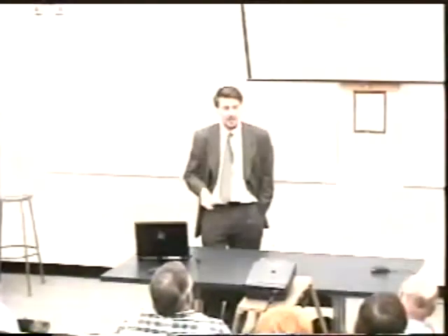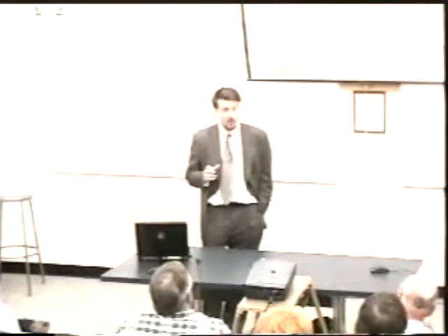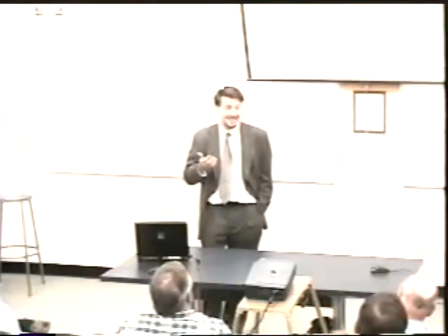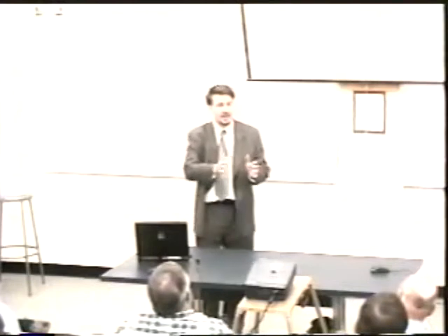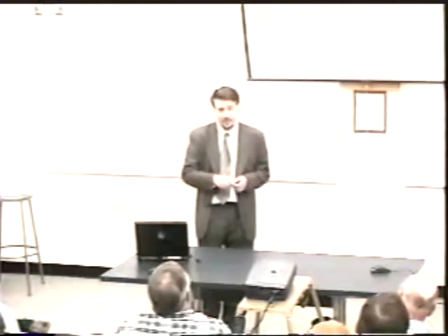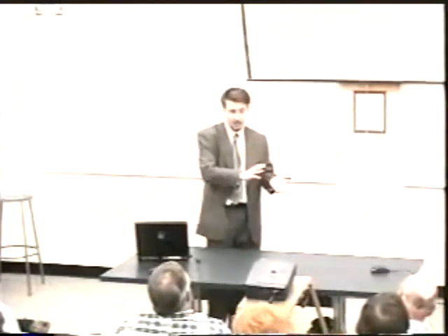One way of doing that is multiple imaging sessions of the same patient. For example, on the prostate, the CT image that we take is only one snapshot in time. The prostate's really moving all around over the course of treatment as the bladder fills and empties, the rectum fills and empties. One way is to take multiple 3-dimensional image sets and develop a timeline of where the internal anatomy is. As far as the localization, how do we correlate something inside of this CT volume to something on the linear accelerator within plus or minus a millimeter?